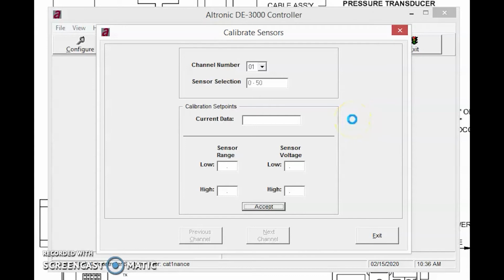It takes a moment to refresh, and it starts out at channel 1. Now you can select any channel you want, but I happen to want to look at channel 1. It tells me the sensor selection is a 0 to 50. It tells me that I have it scaled as a PSIG, and it's showing the current value of a 1.4.